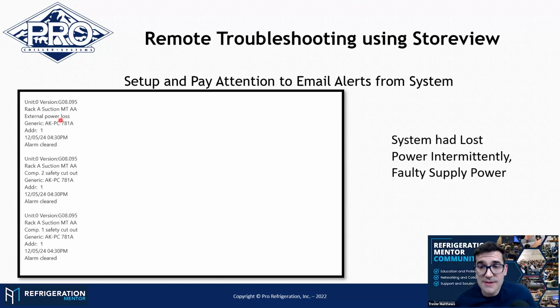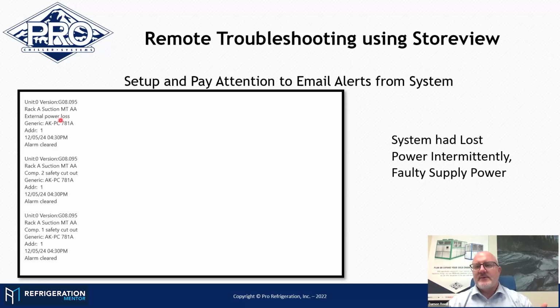And so nothing will get your client happier than you getting in touch with them before they even know that something's happening. Say, hey, Mr. Customer, have you guys had any power issues recently? I noticed the compressor tripped on the chiller, and I also got a trip that there was an issue with the external power. And you're going to get, I didn't even know there was anything going on, or you're going to get, we've been having some power issues. That's awesome that thing shuts down and you let us know, and they're going to appreciate that.